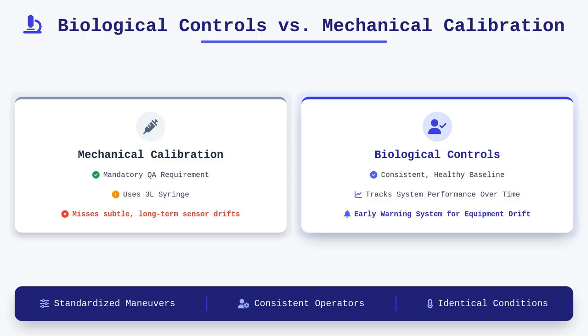Biological controls fill this void by utilizing a consistent, healthy individual, often a laboratory staff member, to perform standardized maneuvers at regular intervals. The primary objective here is not to calibrate the machine, but to track the performance of the system over time compared to a known, stable baseline. By observing the same person repeatedly, you isolate the variance of the equipment from the variables inherent in a diverse patient population. This creates an internal gold standard that provides an early warning system before a piece of equipment drifts outside of acceptable clinical limits.